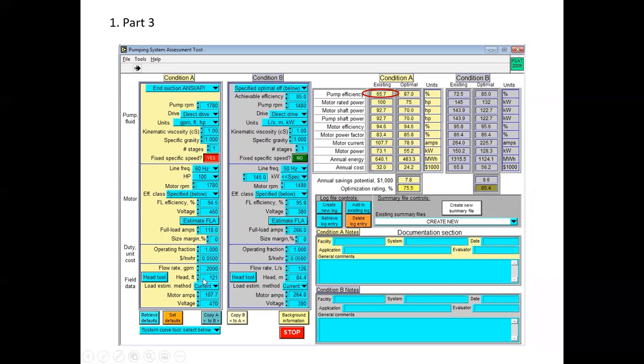We changed the flow rate and changed the head, kept the electrical power because we really didn't change where the pump was operating. We just changed our methods for estimating the flow. And so if we had a flow meter and then went through the head calculation, we would have got a little less than 121 feet. We put that in with our measured electrical. And now we get a pretty good efficiency. I'm not saying it's a good number, but I think our calculation's pretty good. So we get 65.7%. Well, we still say optimal would be 87 under this condition.